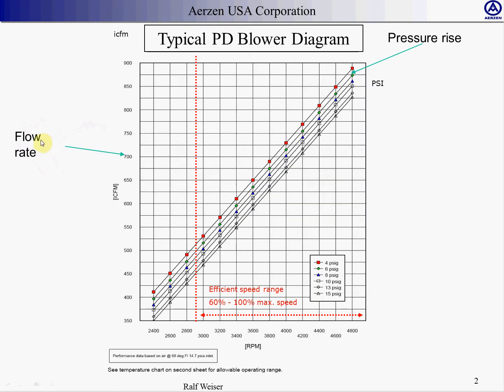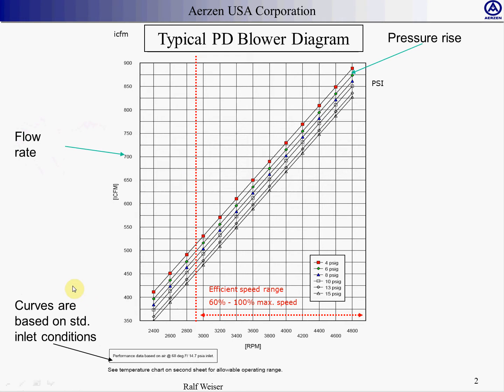The beauty of a positive displacement blower is the linear function between speed and flow. This is due to the fact that the positive displacement machine, as the name pretty much already spells it out, positively locks the air inside the housing between the rotors, and the moment that you turn the driveshaft, it spins out air. This is based on inlet flow in inlet conditions, which means this machine is not all that susceptible to a difference in relative humidity or pressure variance.